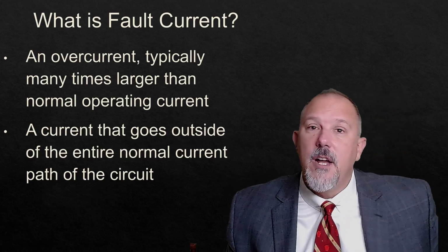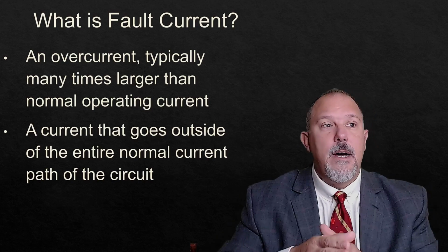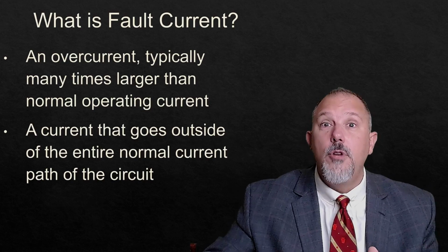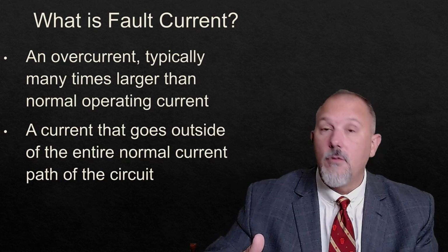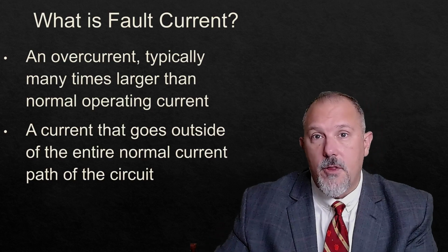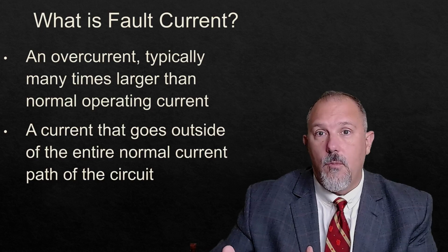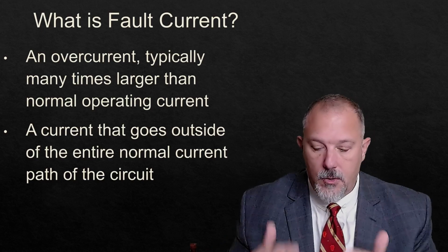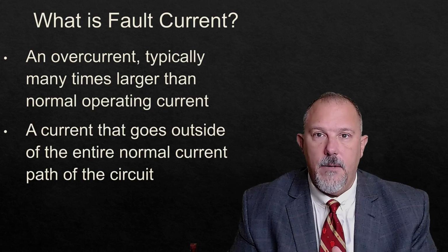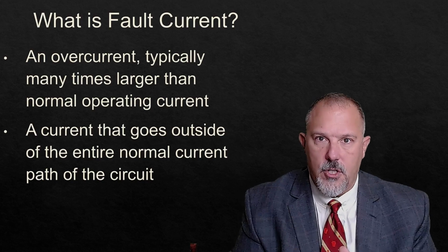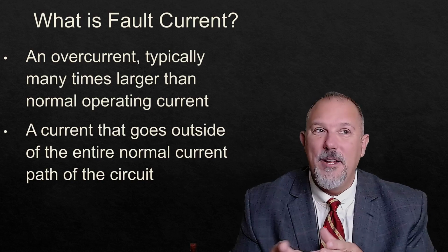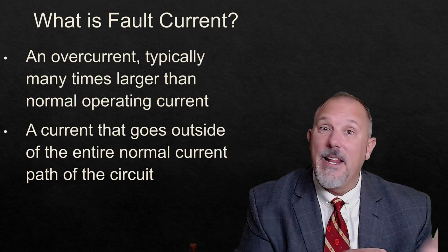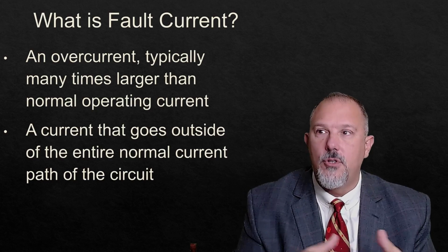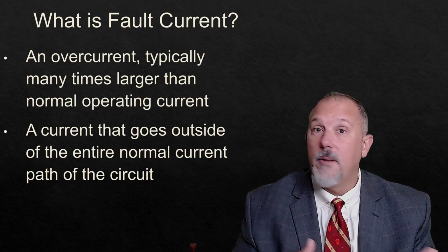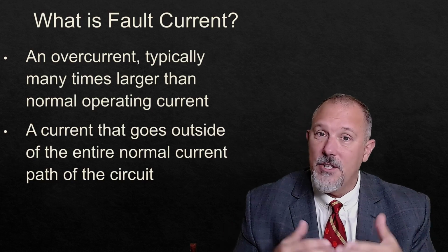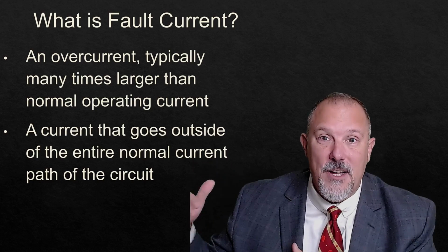And some manufacturers are coming out with circuit breakers that have health indication on them so that you know approximately how much fault current it interrupted, whether it was a short circuit, ground fault, or an overload. So you need to ascertain why the fault occurred.